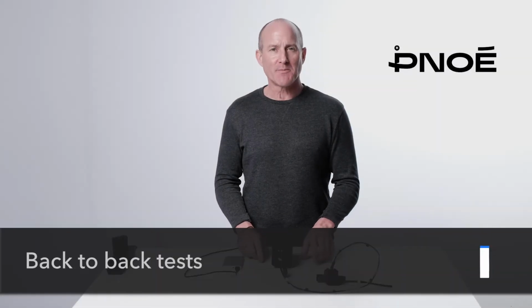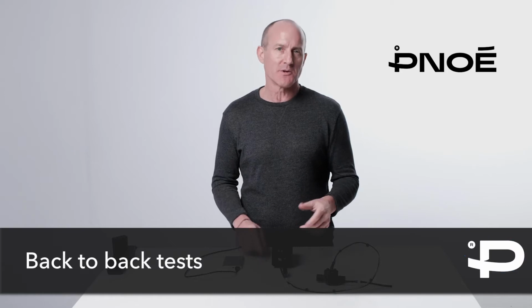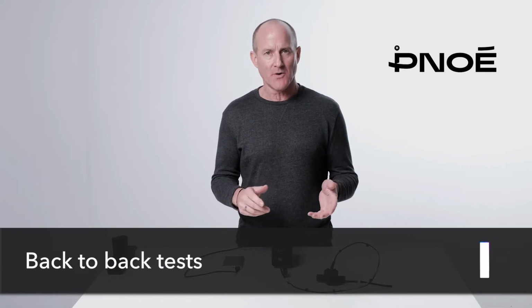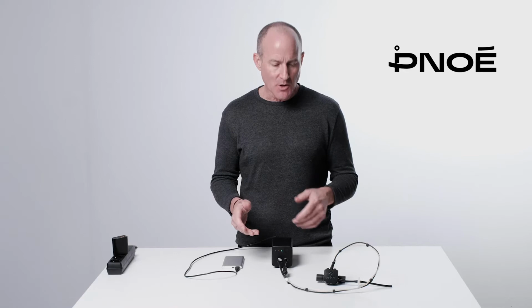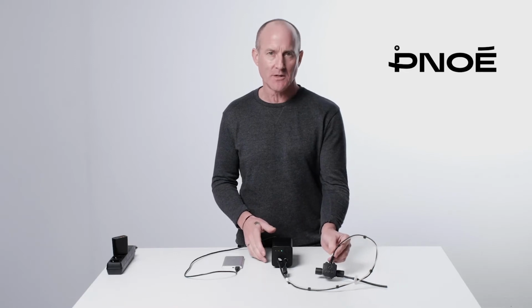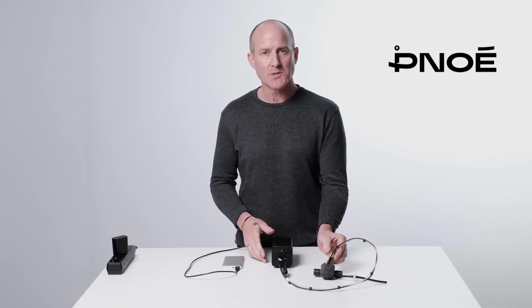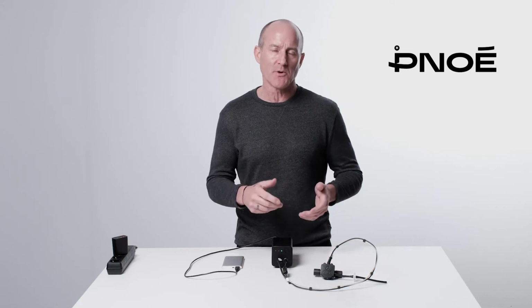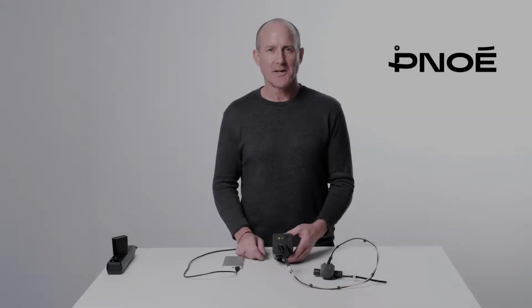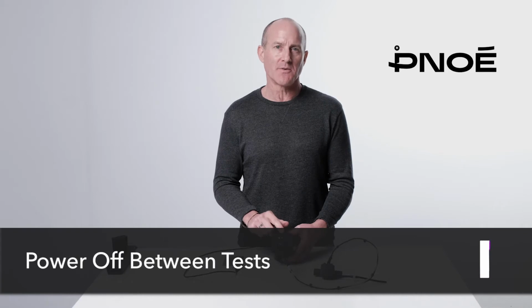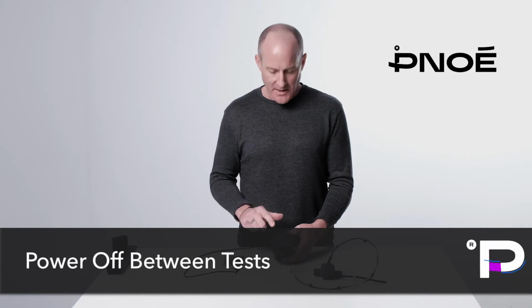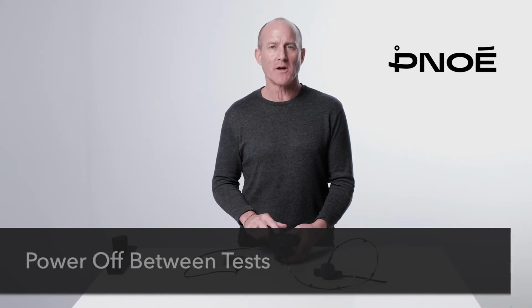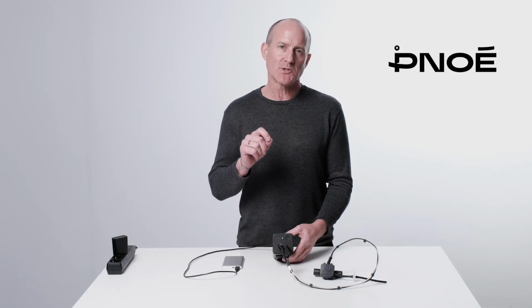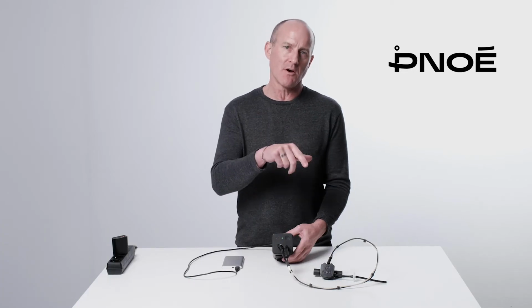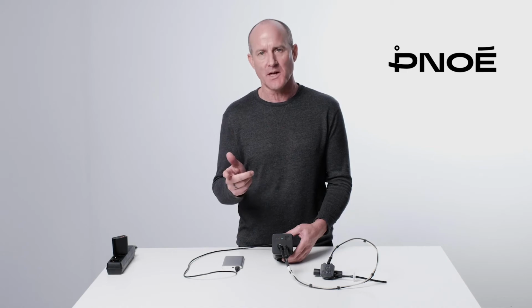If you're completing back-to-back tests with the same person, for example, you're doing an RMR and then following it with a fitness test, there's no requirement for the additional 10 to 15 minute flow sensor warm-up, as it's already warm from the previous test. It's imperative that you turn off and on the device between the tests, as it's important for the internal memory of the PNOE device, and it registers the difference between the end of the RMR test and the beginning of the fitness test.